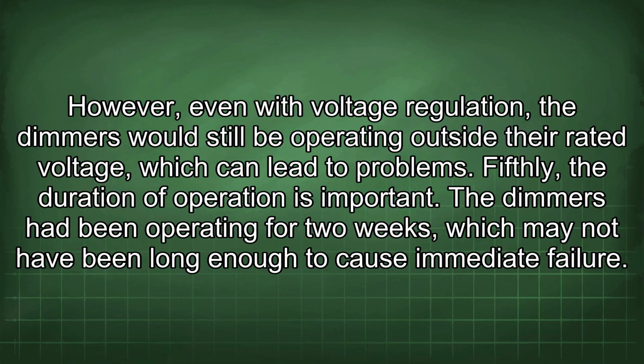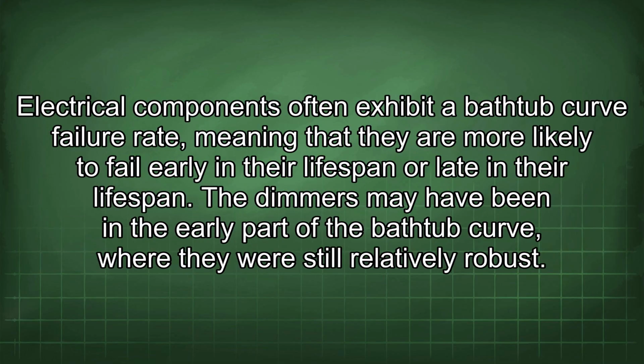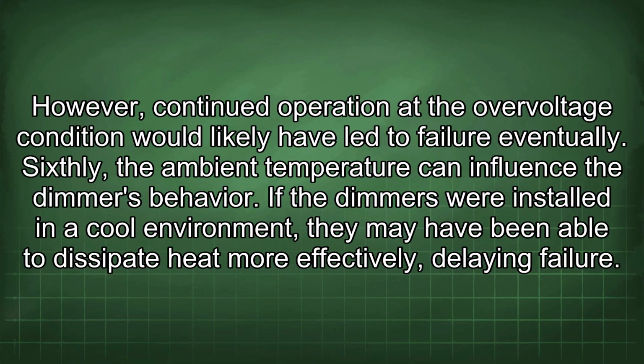Fifthly, the duration of operation is important. The dimmers had been operating for 2 weeks, which may not have been long enough to cause immediate failure. Electrical components often exhibit a bathtub curve failure rate, meaning that they are more likely to fail early in their lifespan or late in their lifespan. The dimmers may have been in the early part of the bathtub curve, where they were still relatively robust. However, continued operation at the overvoltage condition would likely have led to failure eventually.